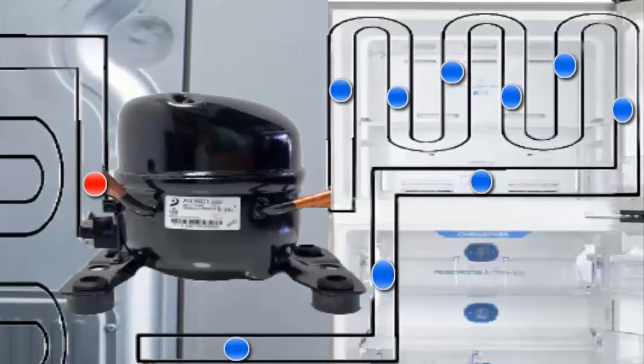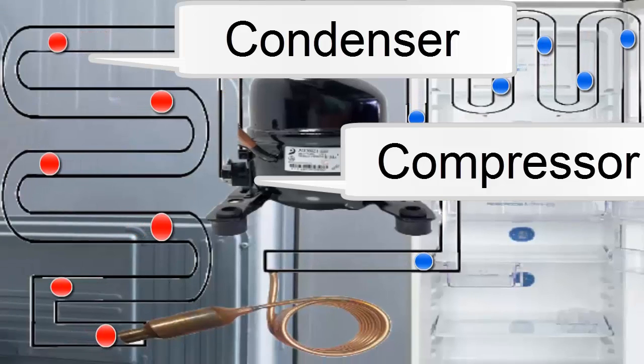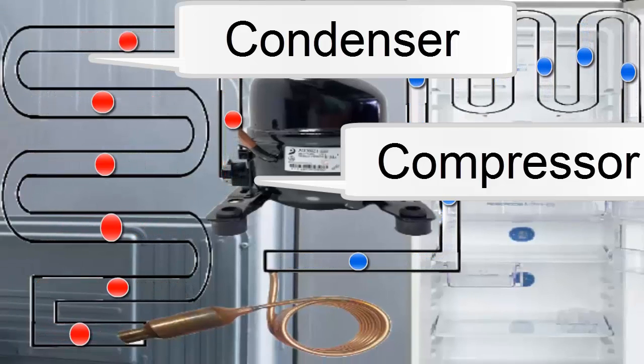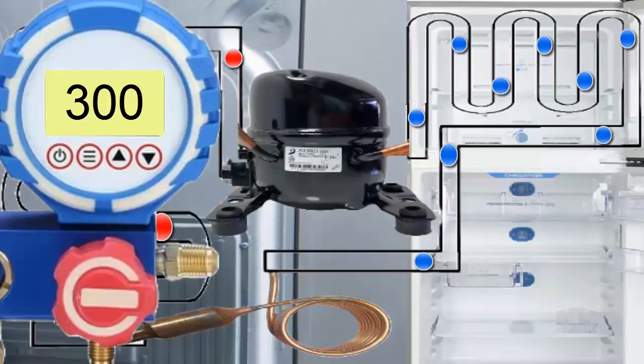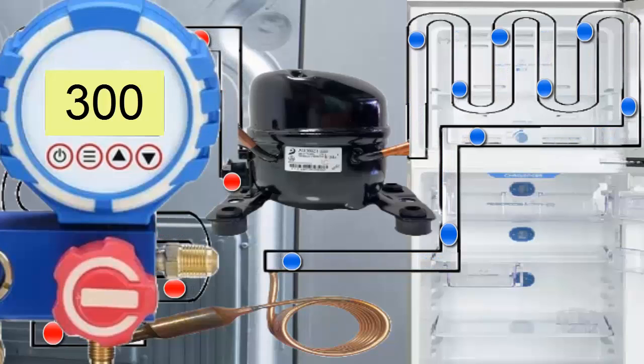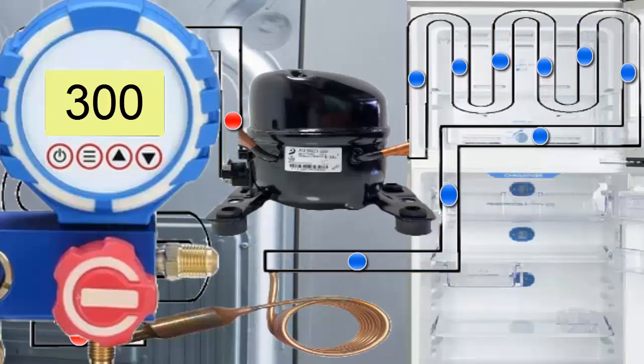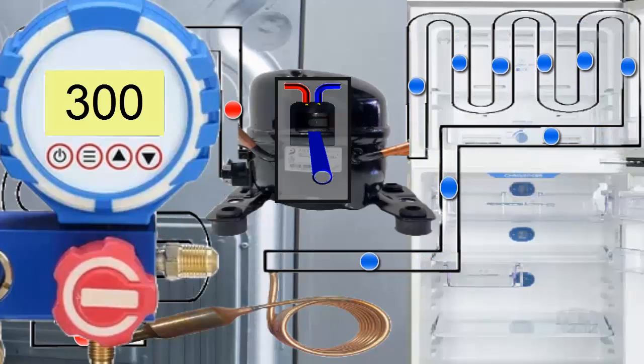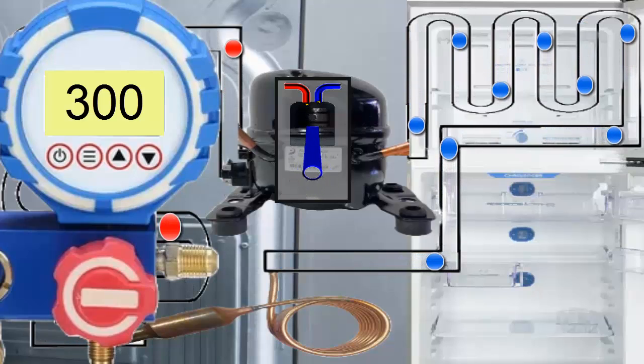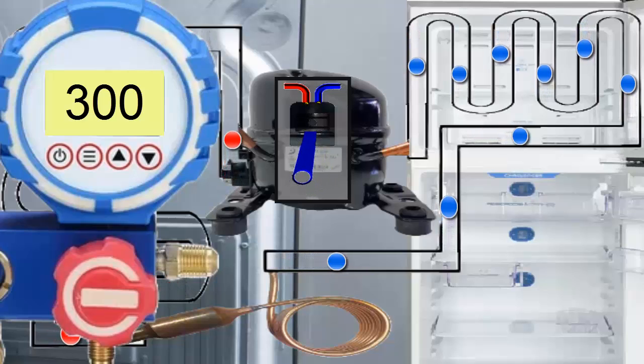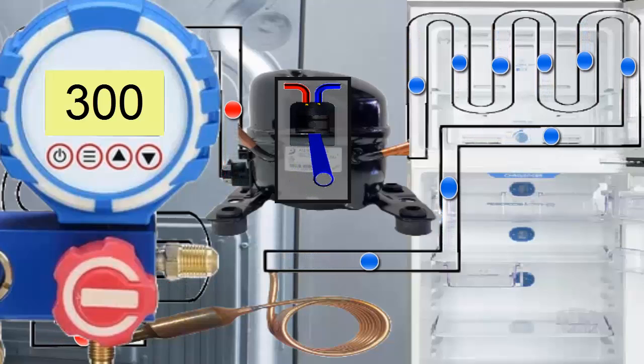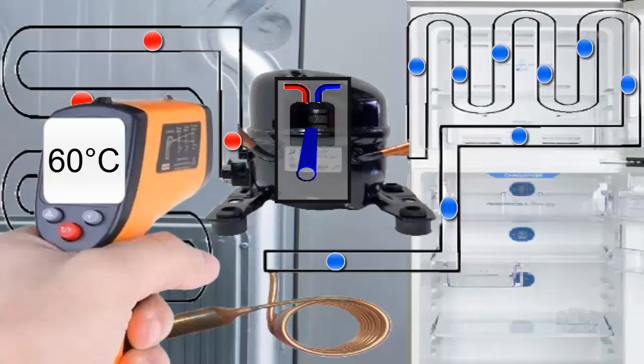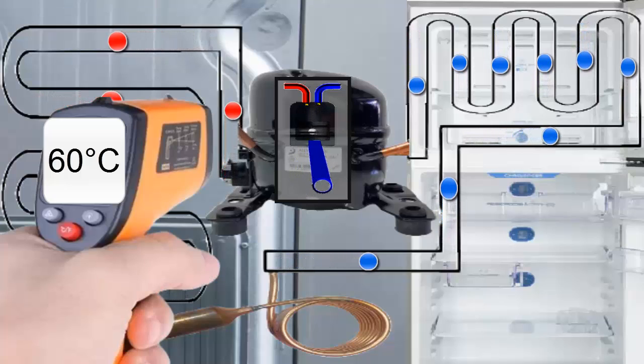The pressure and temperature of the R404A refrigerant increase considerably in the compressor. The pressure of the R404A at the compressor outlet reaches a value close to 300 pounds per square inch. The temperature of the R404A at the compressor outlet can be around 60 degrees Celsius.